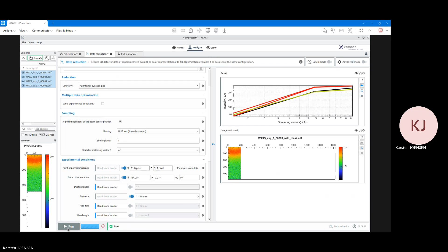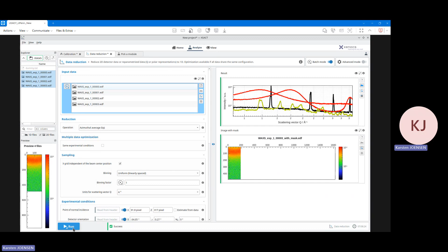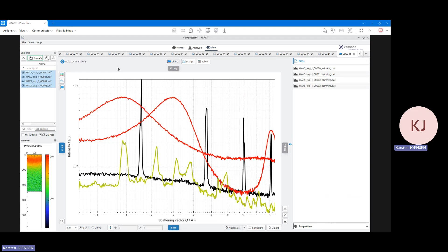And I'm going to do this in batch mode. Did I lose all my files now? No, they're all still there. And then here I go with those files. So those are the WAXS, all calibrated according to the LaB6. Again, if I wanted to change the calibration, I would run these commands here, and then I could take the data after that, and those data would then be put into the header. So 91.8, 317, or alternatively, here 91.8, 317, and 59.